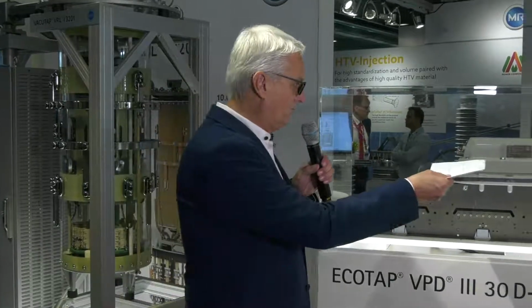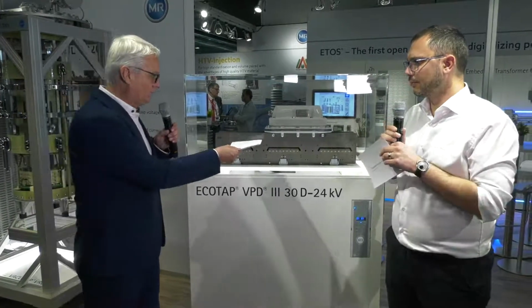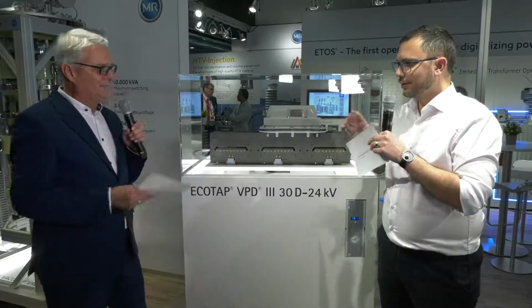I got one question from an OEM or customer who was here during the last days at CIGRE. Now we see the sealing element with the drive directly connected to the tap changer itself. Some told me they have an air or gas cushion because they don't have a conservator for DT transformers. I do think this is also available with some spacing in between if you have an air cushion on the top level and things like that.